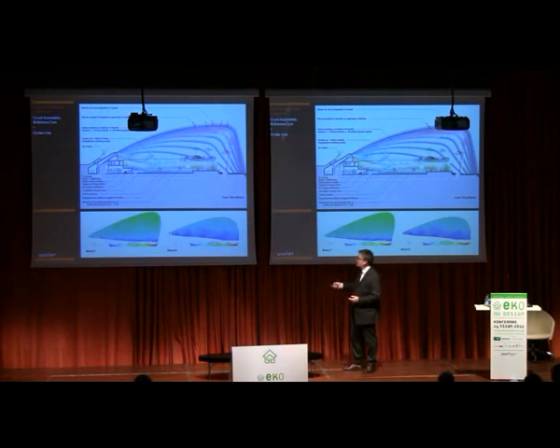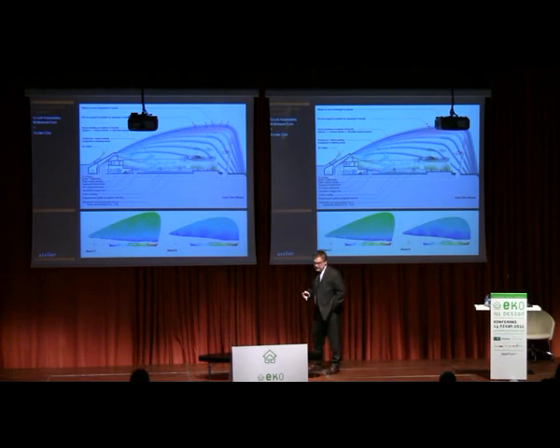This is some CFD modeling, computational fluid dynamics, to prove temperatures at low level where the people and the root systems are, and then we were allowed to let the temperature rise as the building got higher. So again, we're using displacement, displacing the heat up out of the occupied zone. All the paving has chilled water pipe work in, and we have air distributed out at low level at a very significant volume, about 100 meters cubed a second in one of the biomes.